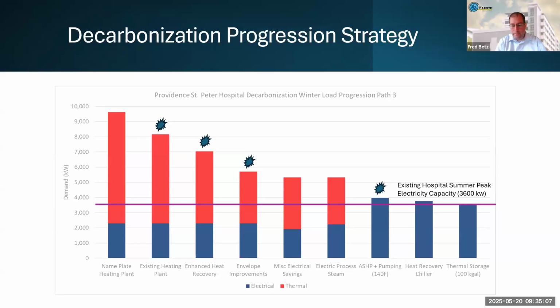And then finally, not last, but definitely not least, and it's actually one of my favorite topics here, is thermal storage. So traditionally, thermal storage is looked at from a cooling perspective to provide peak demand management for cooling systems. In this case, we're actually storing hot water, and we're actually storing it in the location of the 2 large steam boilers in the existing central plant. So as these demand side measures and new plant come online, we're able to decant that load and eventually remove those. There's a whole phasing study that we're not going to go into in detail here, but enabling that transition, because the challenge here has to be running the whole time as you're making these updates. Next slide, please.